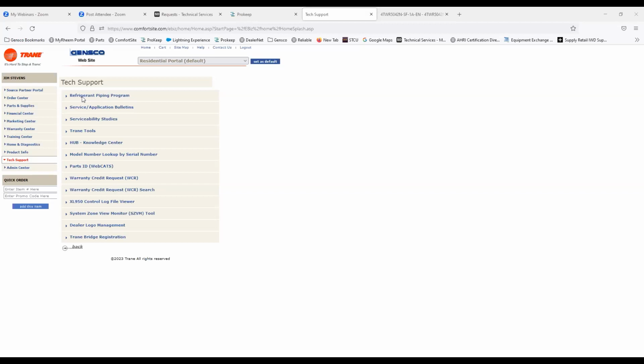We will select a 3-ton unit. And it populates the refrigerant type automatically, even though we already know it's a 4, so that's for 410A. It tells you what kind of refrigerant. Then we're going to go over here. We're going to select the location. Is it above or below or horizontal to the indoor? So the outdoor is above the indoor in this case. My total line length is 75 feet. My vertical change is 20 feet. I have 0 short elbows because we don't use short elbows. We only use long elbows. I'm going to have 6 elbows and I'm going to have no underground tubing. I'm going to hit calculate. It's going to tell me the line set size that I can use, 5/16 or 3/4. I'm going to need to add a compressor sump heater and an indoor TXV because of the length of my line set. Okay.